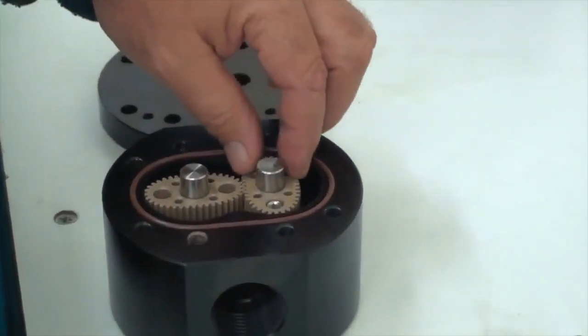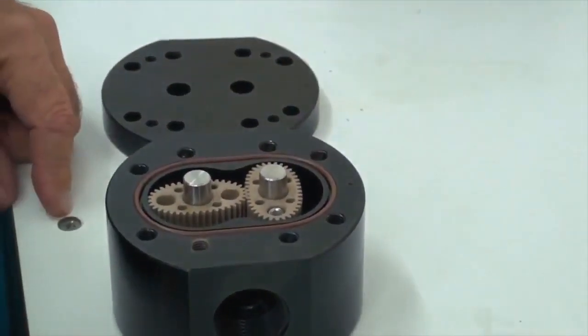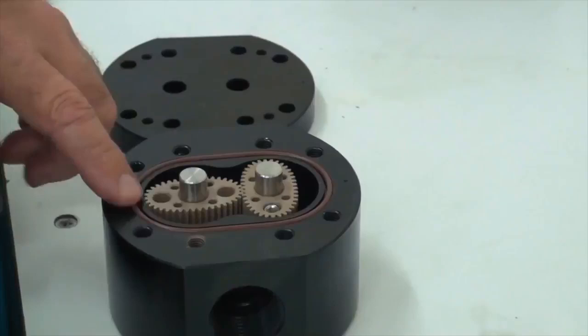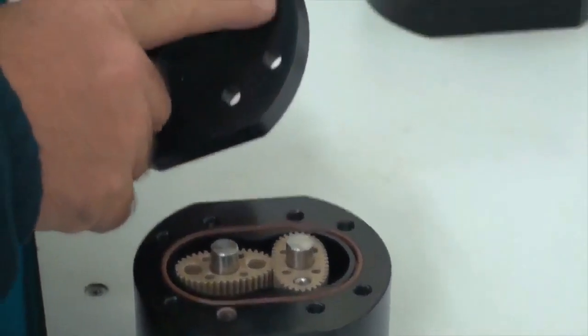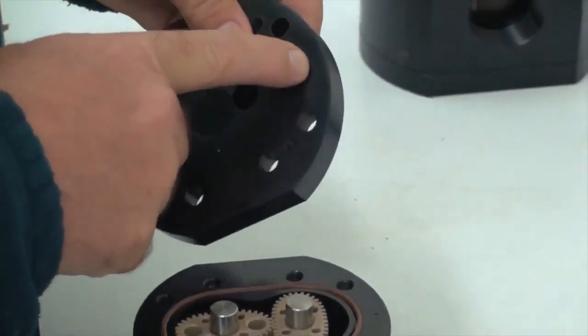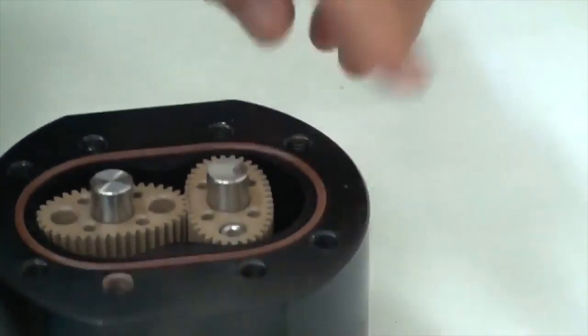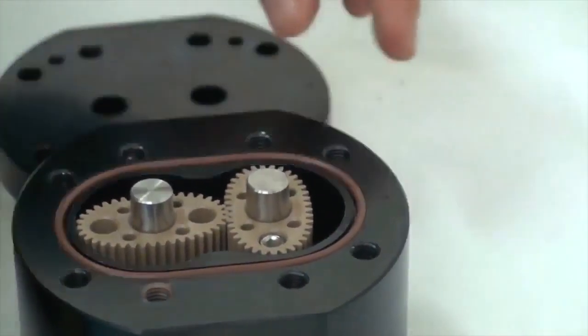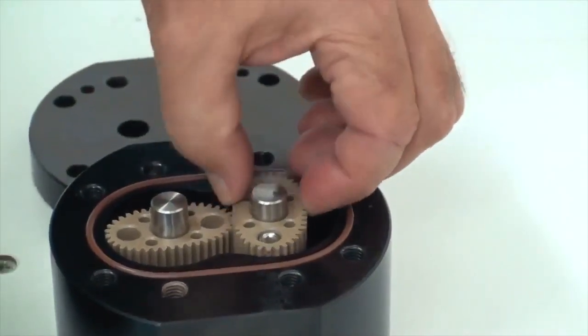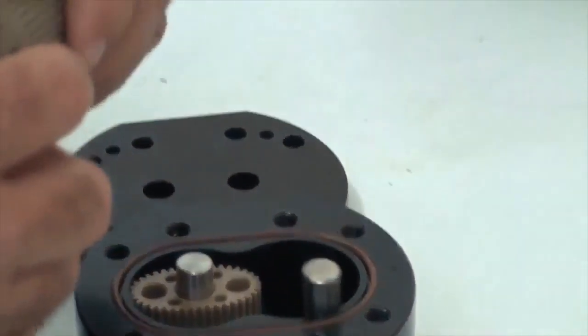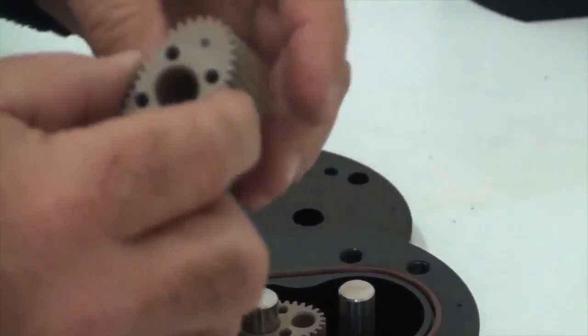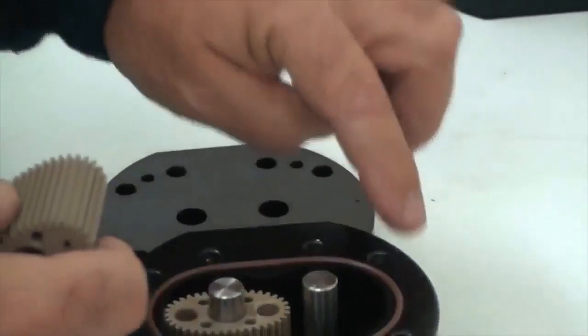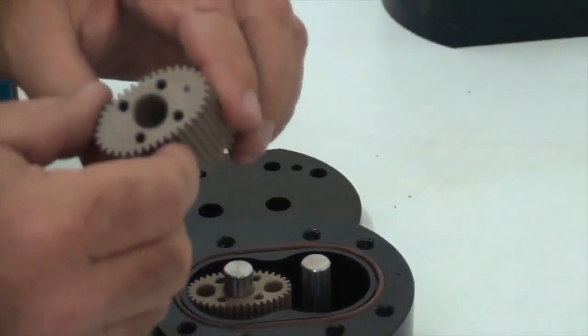It's a good idea to make a note or use a pen to mark the rotors and where they sit. On the new MX range we have what's called a dimple, a little dimple just at the top there. This signifies where the active rotor sits, and the active rotor has a dimple on the top. Those three dimples must go together when we reassemble.